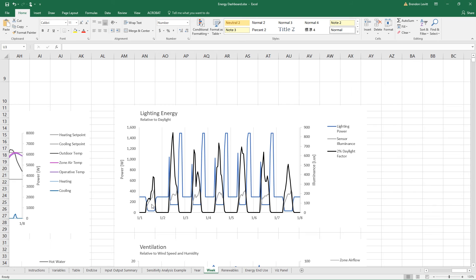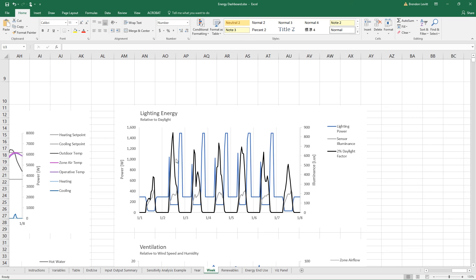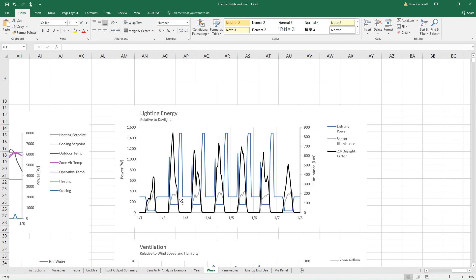And you can see the blue graph here is the lighting power. The gray is the sensor illuminance. And the black is a 2% daylight factor, which is a theoretical value if you had 2% of the available daylight inside the zone. This is a common value for a well-daylit space is a 2% daylight factor. So this gives you a sense of how bright a well-daylit room is compared to what your room is or where your sensor is placed, at least.